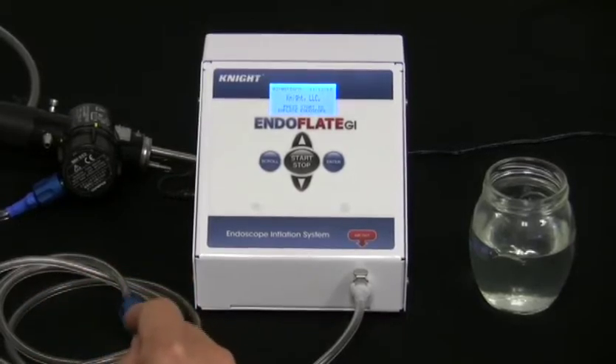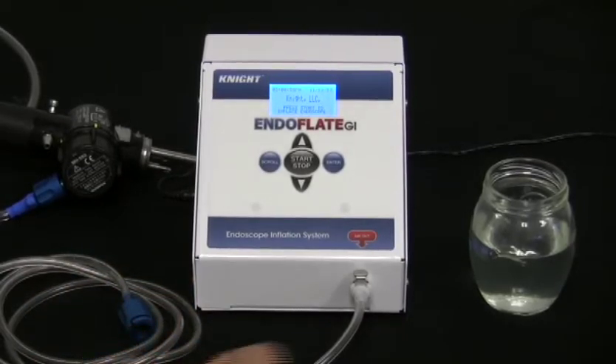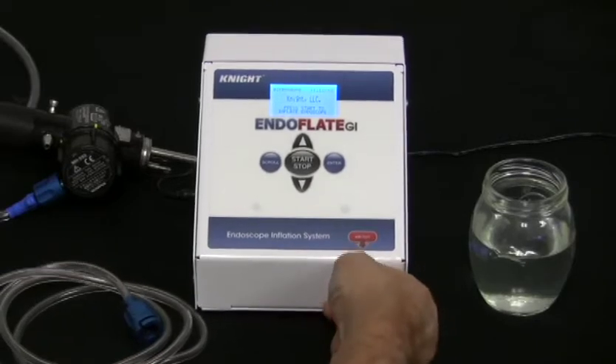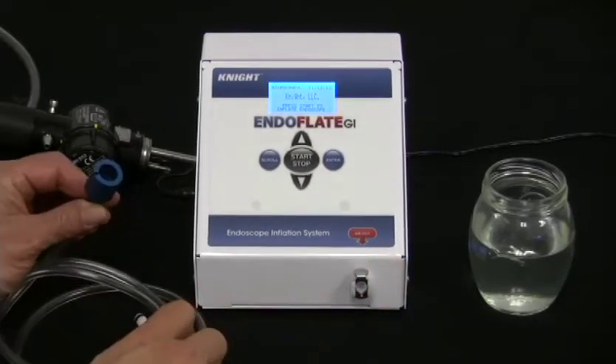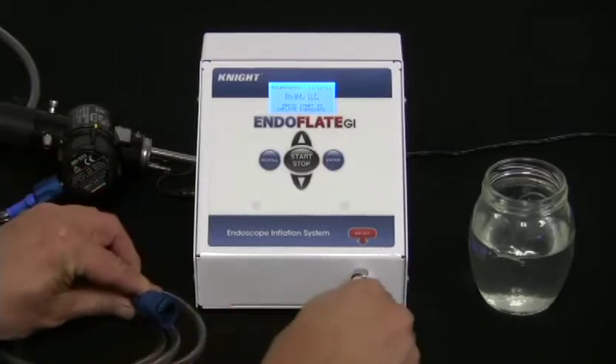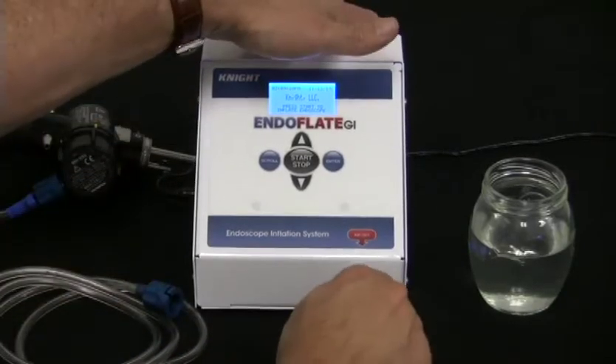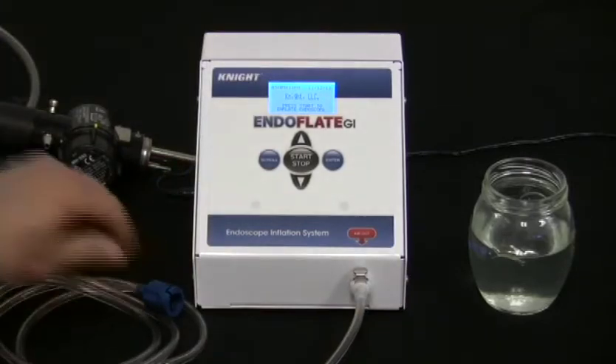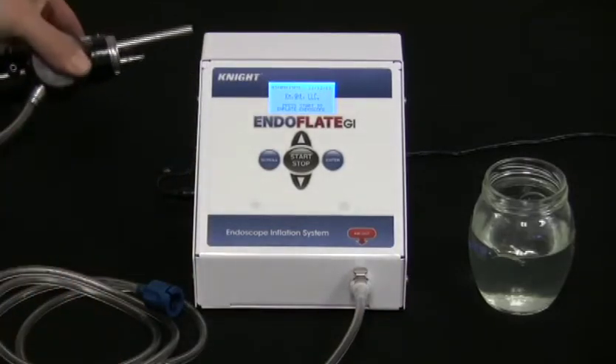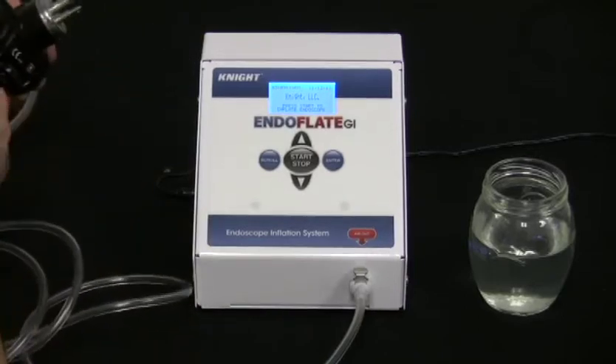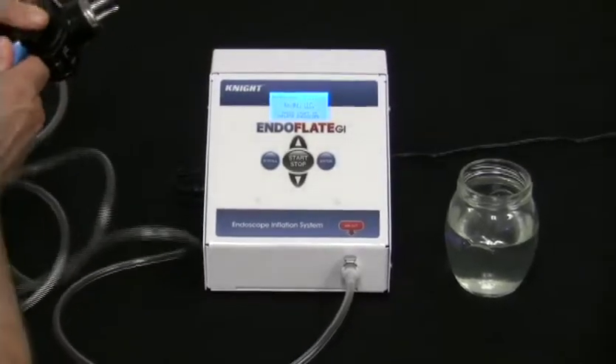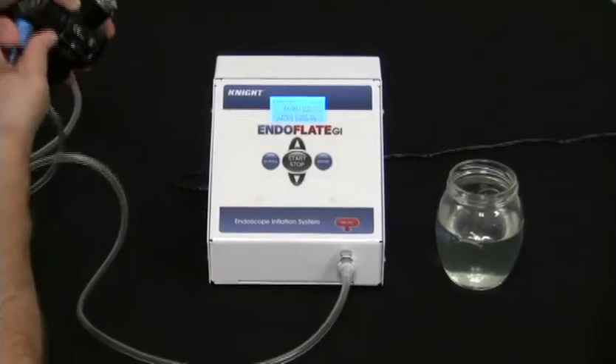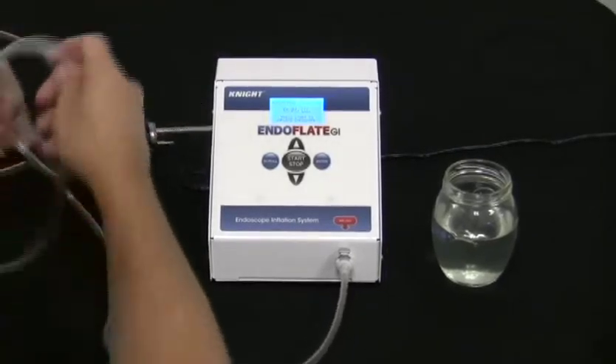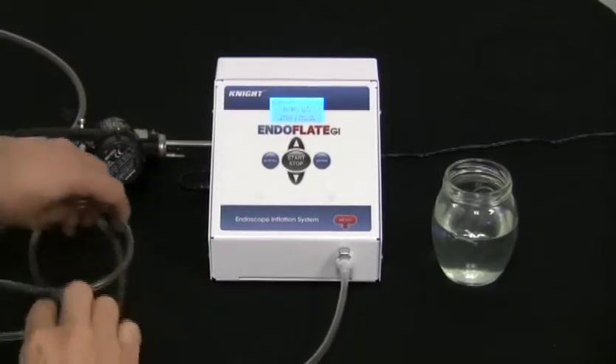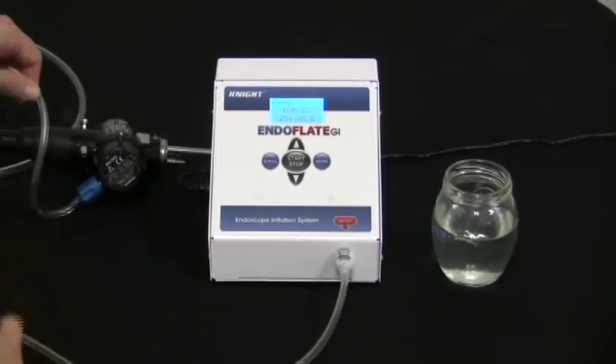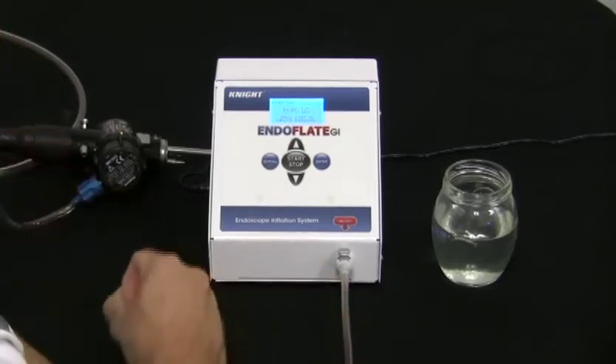To operate the system, like most any other leak tester, you're going to have a leak tester tube, and of course the manufacturer's ETO valve connector. This one here happens to be for an Olympus. So once you're connected, I'll take this one off of here, I'll put her on the duodenoscope we have here, push it down and twist it on. Of course, the technician is going to start the test on top of the counter, and all I need to do is hit start.